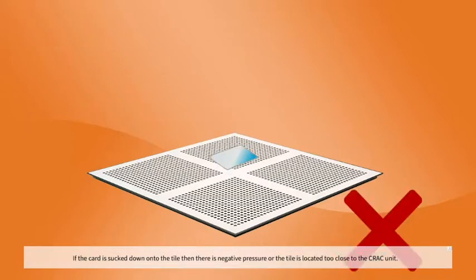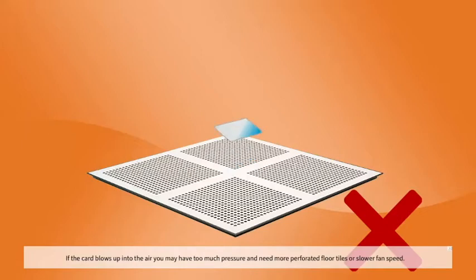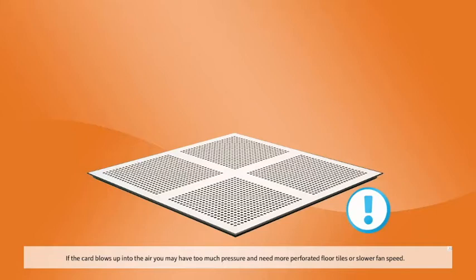If the card is sucked down onto the tile, then there is negative pressure, or the tile is located too close to the CRAC unit. If the card blows up into the air, you may have too much pressure and need more perforated floor tiles or slower fan speed.